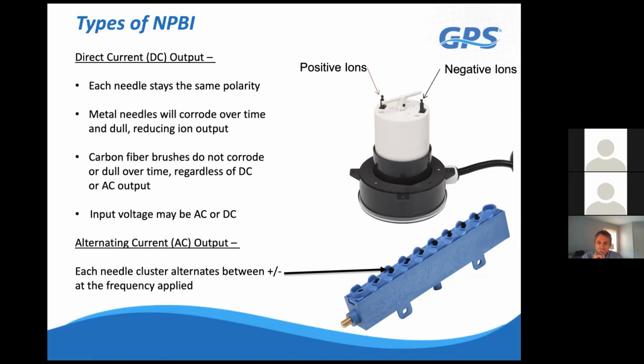So that's a huge benefit to the owners, and especially as it relates to COVID-19, you want the ion density at maximum all the time. So you don't have to worry about a maintenance crew going out and cleaning the systems to maintain their output. They maintain themselves all the time. And so with a DC system, it's highly important to have this auto cleaning feature, as well as I want to point out with the DC system, that really only refers to the output. The input voltage to power the system can be AC or DC.